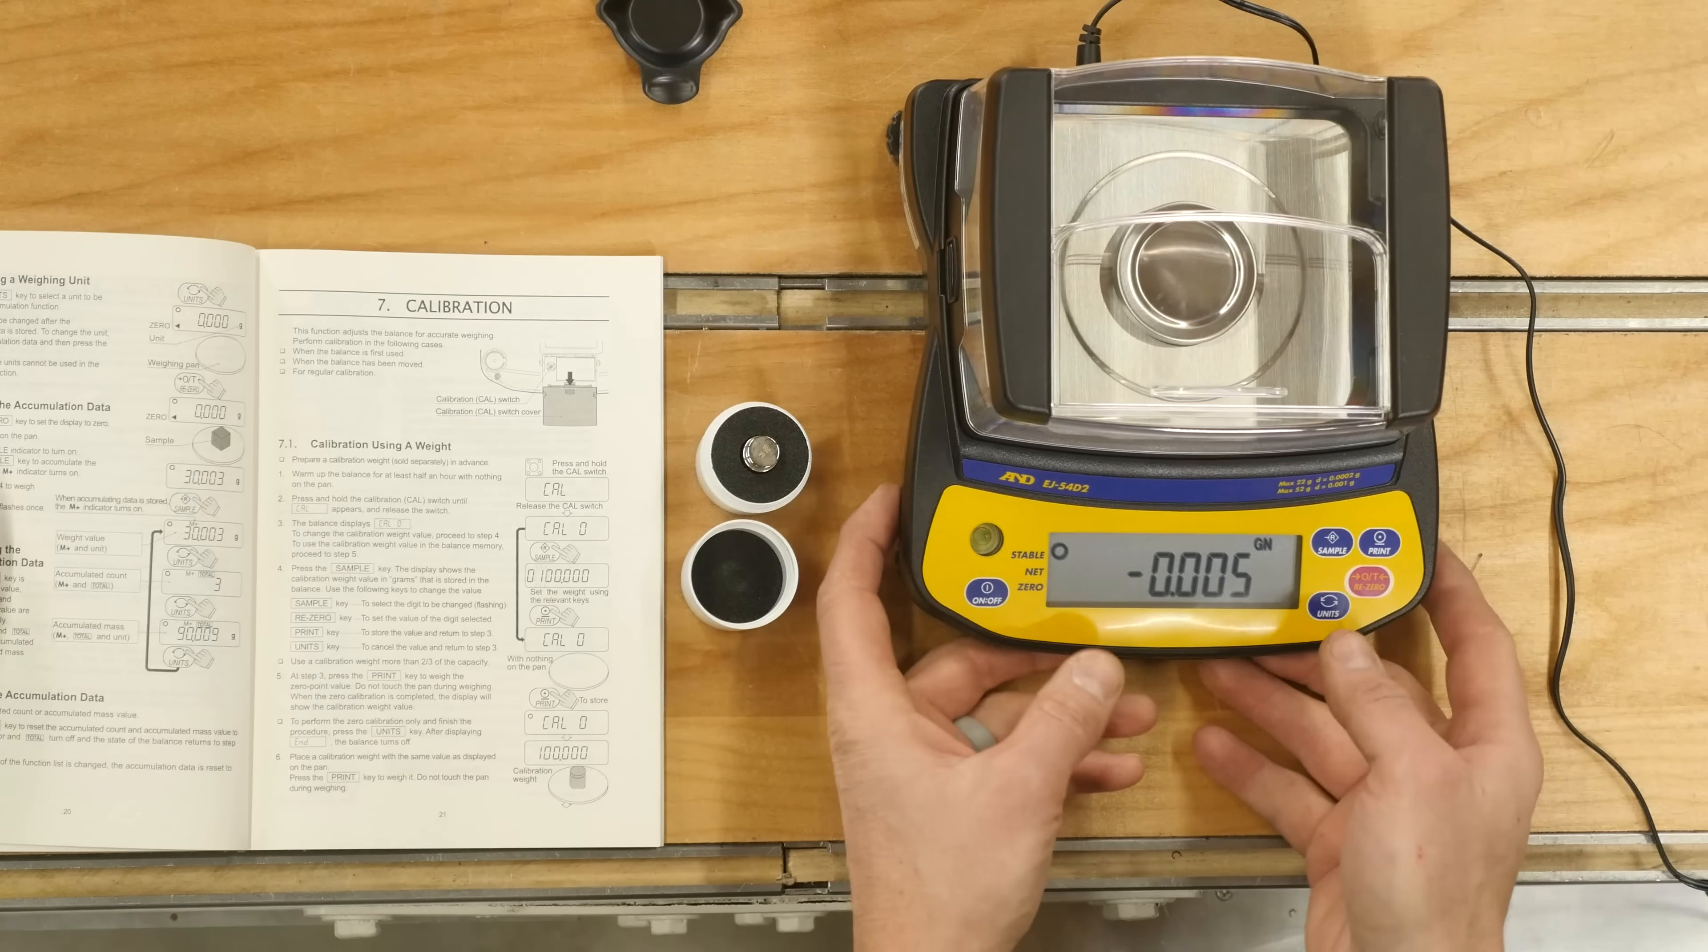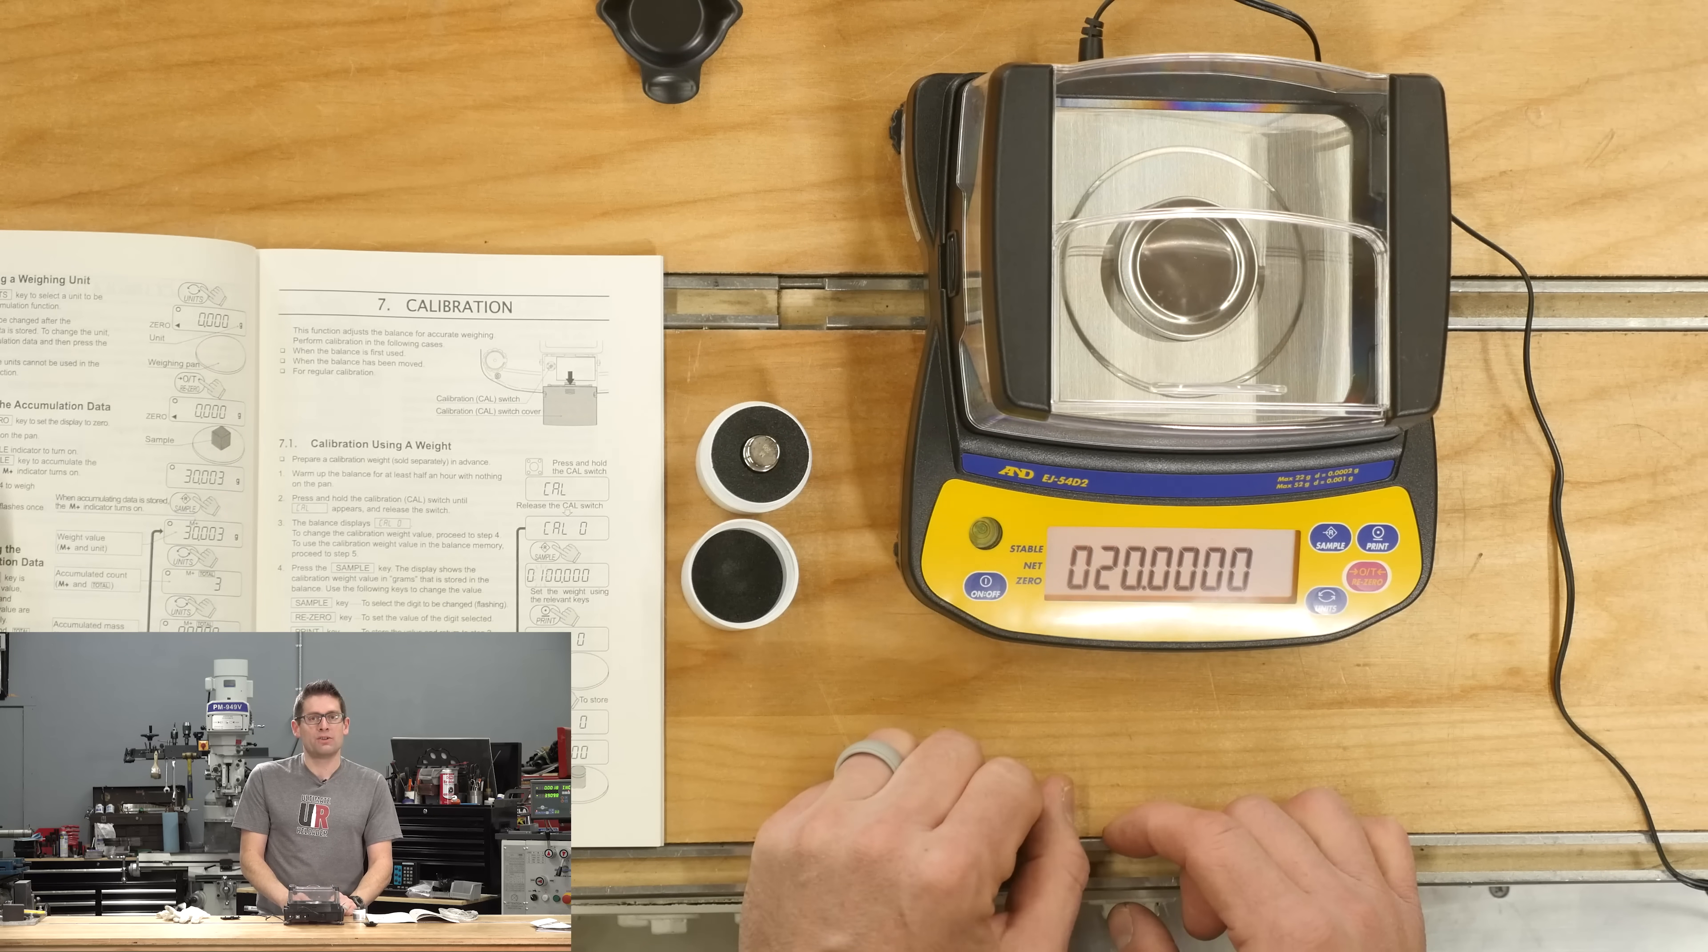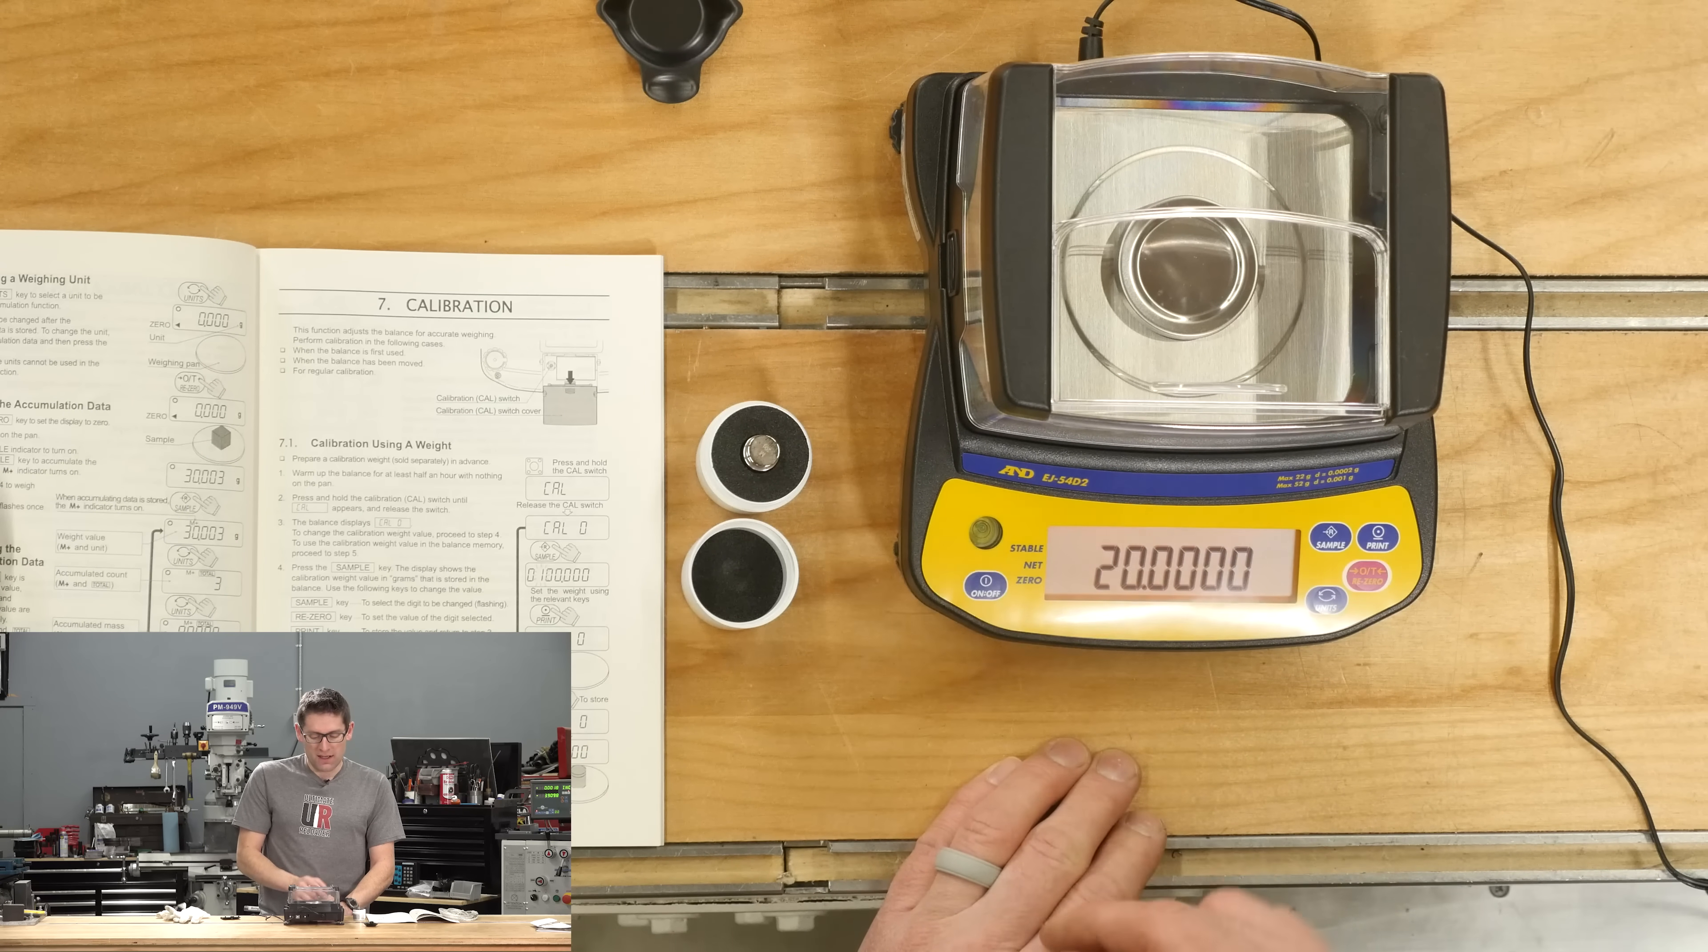Now, to calibrate, there's a little plastic door under the front of the unit. We're going to pop that off, and there's a tiny little button here. We're just going to hold that until it displays CAL. I have a 20-gram weight that I got separately from Cambridge Environmental, and if we hit sample, it's going to show us what the calibration weight is that the scale thinks we're using. It says 20 grams. If it's not matching here what you have, you can very easily change that. We're going to hit print to calibrate just with the platen, and then it says 20.